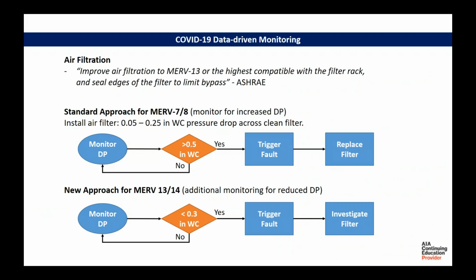First, to air filtration. So this goes back to fault detection. And one of the most widespread analytics that people put in place, and I think it's a perfectly fine one, is to monitor pressure drop across an air filter. So usually when you install a MERV 7 or MERV 8 filter, which is standard, you'll get 0.1, 0.2, in and around that range, pressure drop for a clean filter. So we bring that data, it's in an automation system, it's in a fault detection platform, wherever it is, we monitor it. And when it gets to a 1/2 inch pressure drop, a 1/2 inch of water column, then we have a dirty filter. And we want to change that filter because it's dirty. The data is telling us it's dirty.